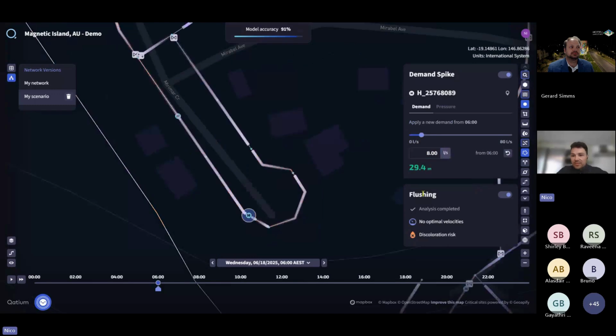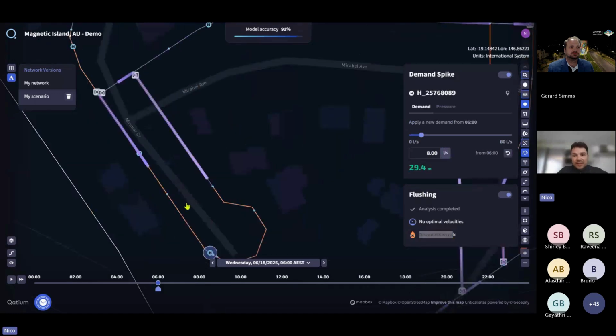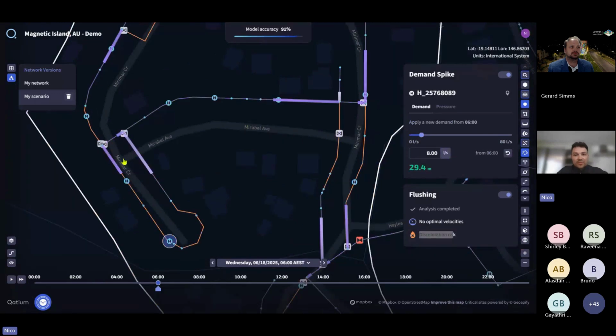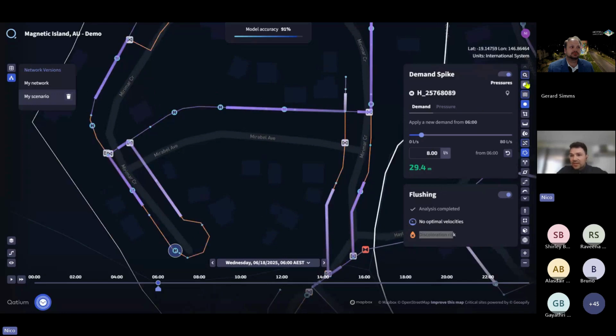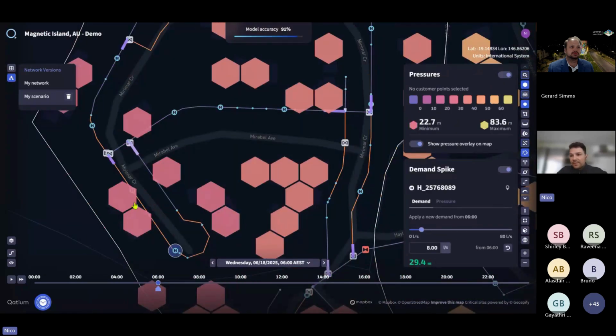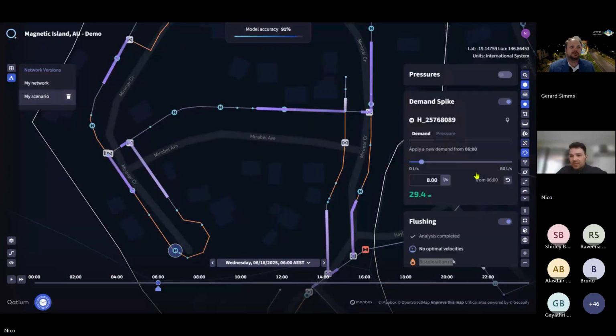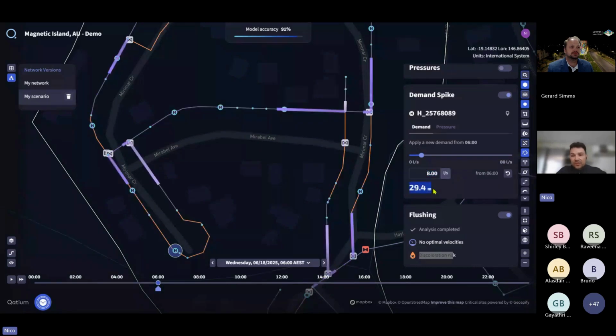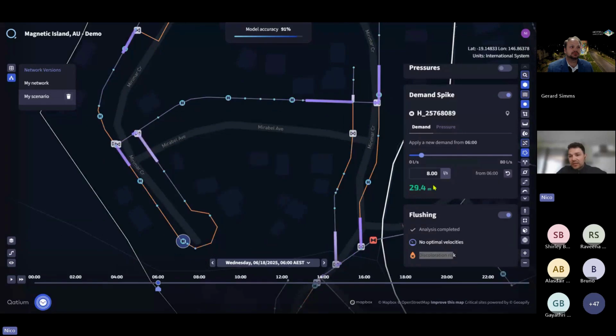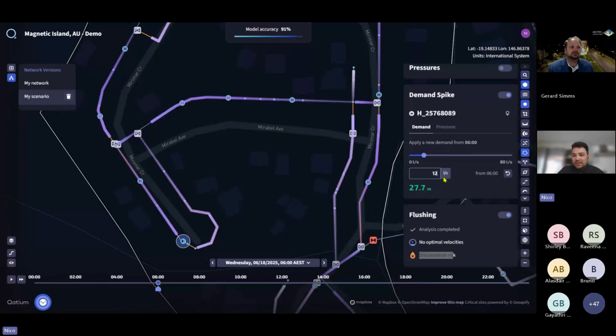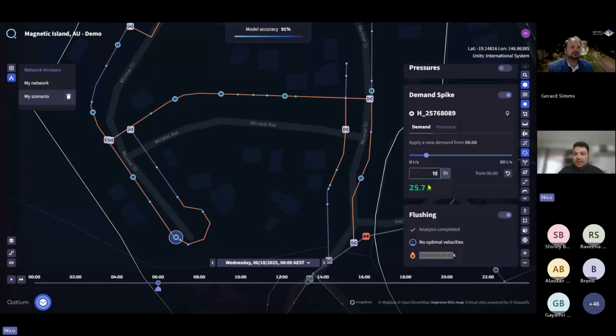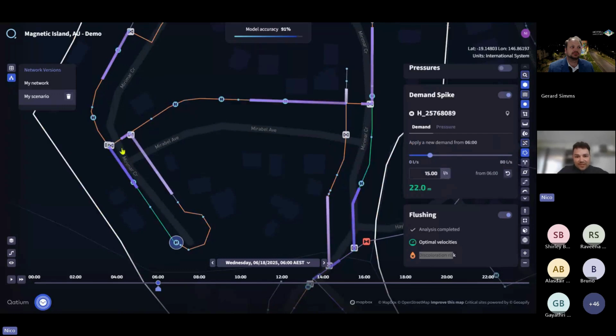The plugin advises you of discoloration risk in yellow, and in green: once the pipe has reached the optimal flushing velocity, it will turn green. You can also assess your pressures in the network at the same time, to ensure your customers are still receiving the correct pressure service level. The plugin also tells you your residual pressure, so if you have a minimum, that can guide you to ensure you comply with it. You continue to increase your flow until you reach the optimal velocity in the network. If the pressure drops too much, you can start considering closing valves around to limit the capacity and ensure a higher velocity along the main you want to flush.